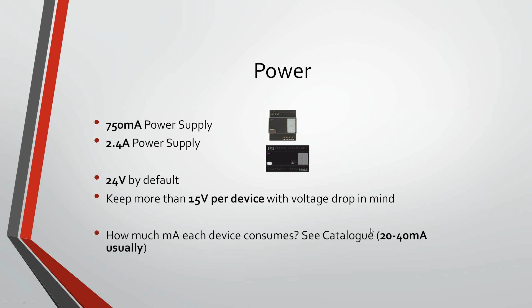24 volts voltage is used by default. You should keep more than 15 volts per device and keep voltage drop in mind. If you need to know how much milliamps each device consumes, you go to the catalog, and usually each device consumes from 20 to 40 milliamps, but some of them consume more.